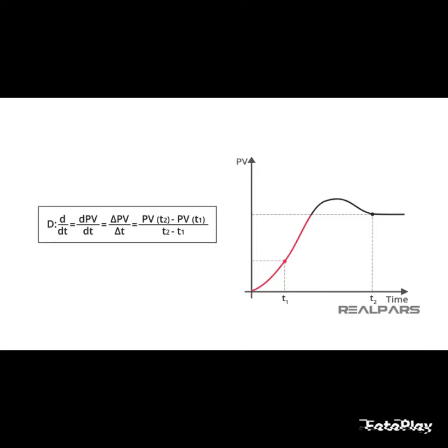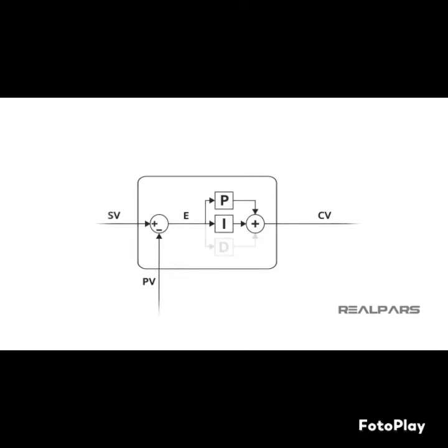However, since the derivative term is measuring the rate of change, the process variable must be a very clean signal, meaning no noise within the signal. For that reason, derivative terms are not often used in controls. The most commonly used controller is the PI. Most processes can be well served with this type of control. P and PID controllers are occasionally used while PD controllers are rarely used.